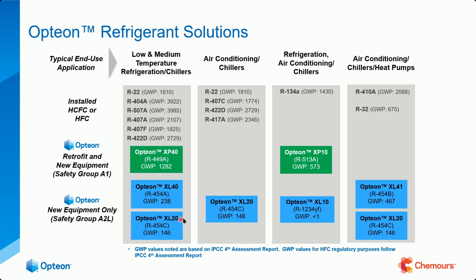That'll be your 454A. On applications with more than 200 pounds that have to have less than 150, that'll be your 454C. 454C was made purposely for that reason, anything over 200 pounds. 454A was the first design. This was after the EPA set the guidelines for over 200 pounds, okay? And this will only be used in new equipment. Anything that's in a blue box will not be put into any of these existing systems, pardon me. They're not designed for A2L equipment.